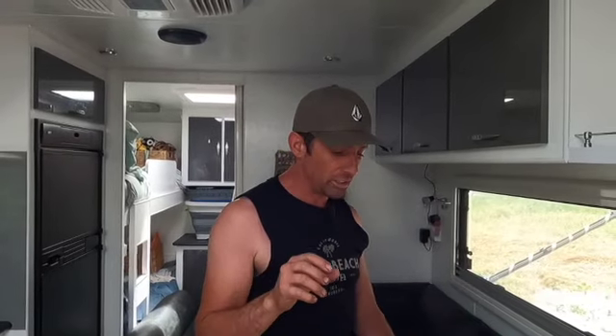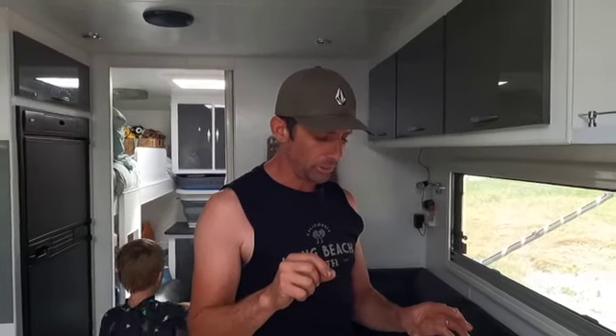The reason I'm talking kilowatts and not amp hours is because amp hours doesn't give you a proper indication of capacity unless you're referring to voltage. You have to refer the voltage to the amps. What I mean by that is, this is actually a 24 volt battery, not a 12 volt battery. But if I was to say this was a 400 amp hour battery without referring to the voltage, it doesn't tell you what the capacity is if you don't know what the voltage is. So 400 amp hours at 24 volt is not the same as 400 amp hours at 12 volt, it's double the capacity. But if I'm talking kilowatts, kilowatts is not based on voltage.